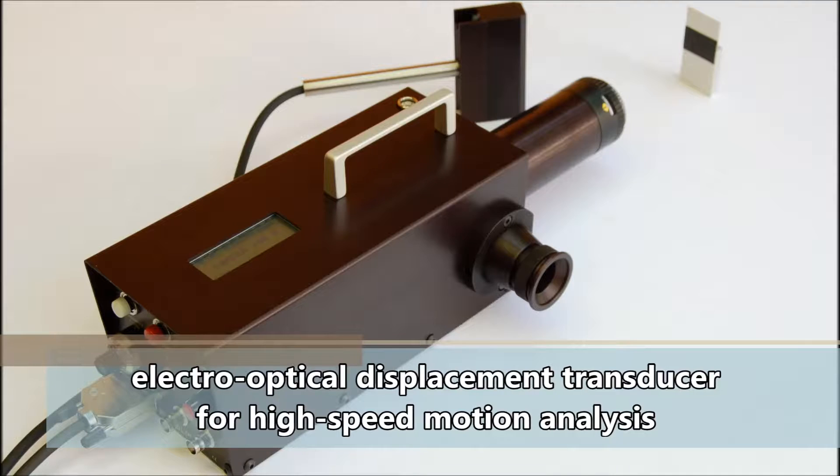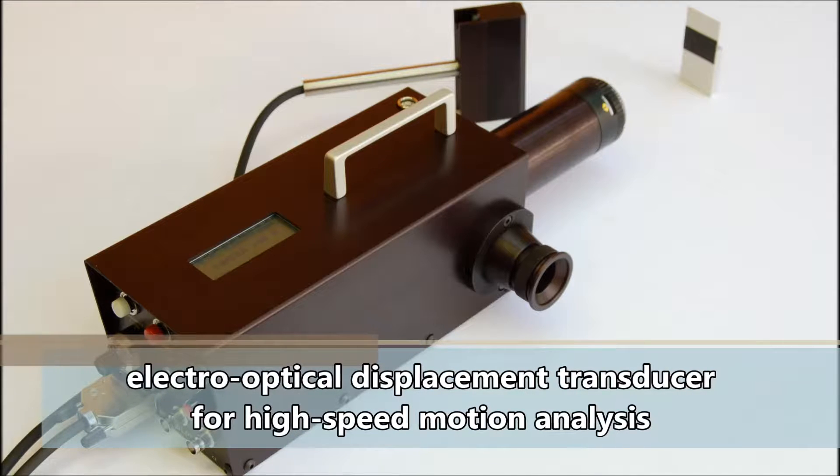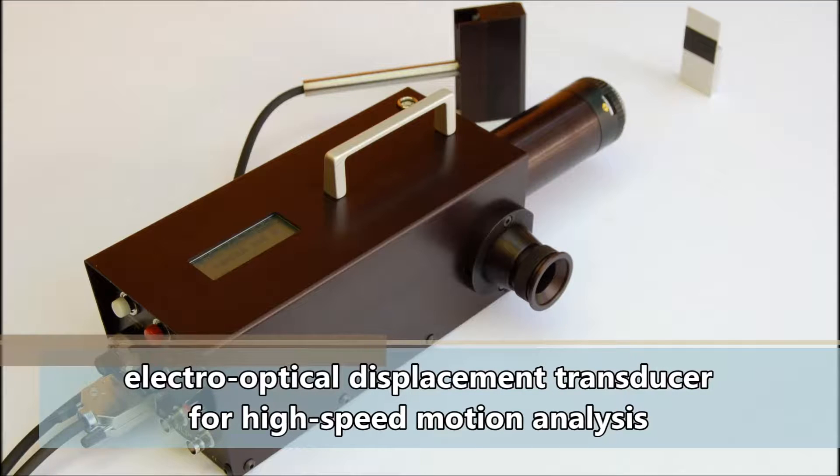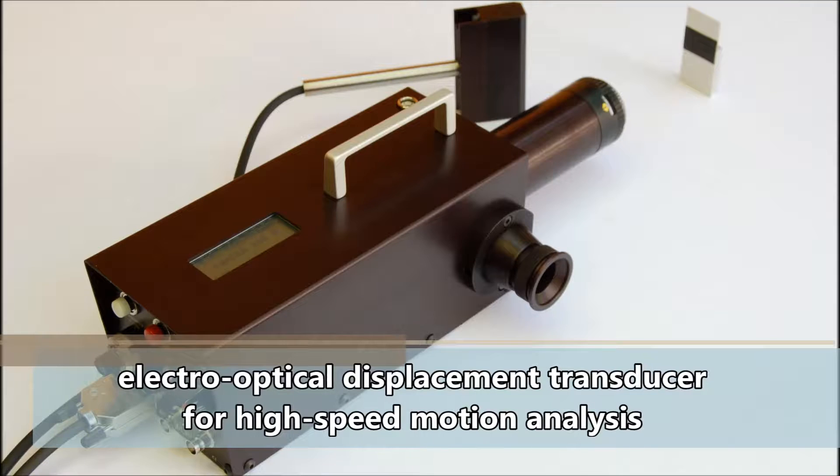Model 100R is an electro-optical displacement transducer designed for high-speed motion analysis. It contactlessly measures the motion of a black and white edge on a material sample.